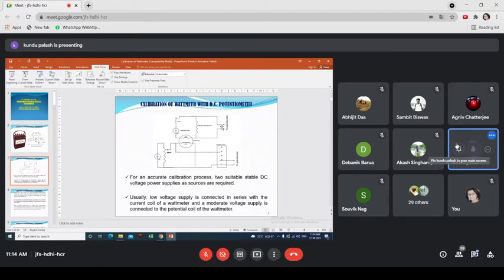So this is an unknown voltage and this is an unknown voltage. This voltage is a measure of the potential coil voltage, and this voltage is a measure of the current coil current. So these two voltages are measured finally by dividing the resistance value. Here the current coil current can be measured.